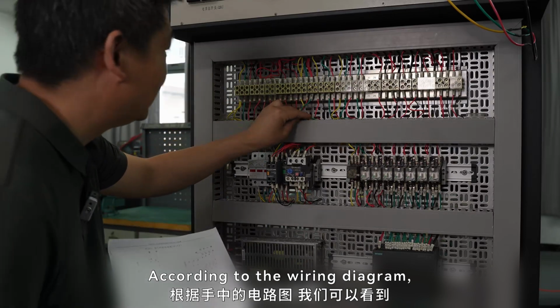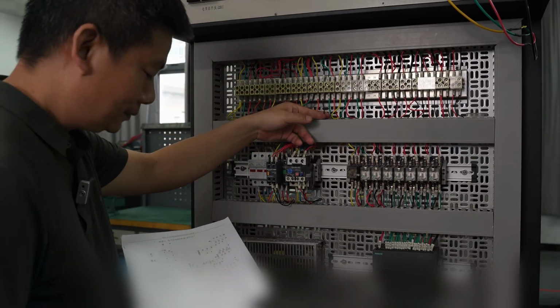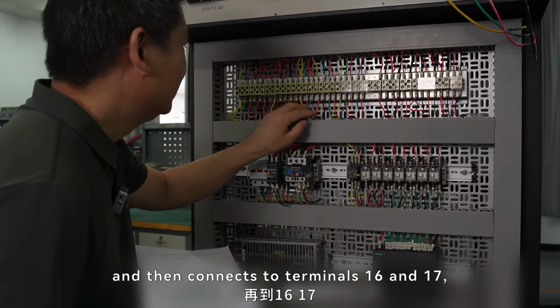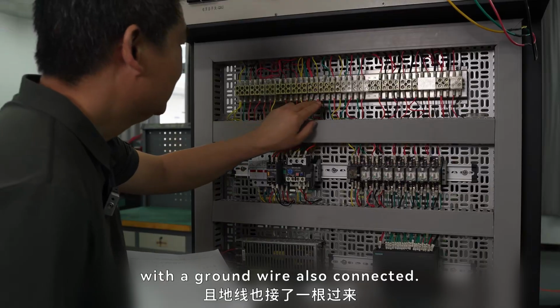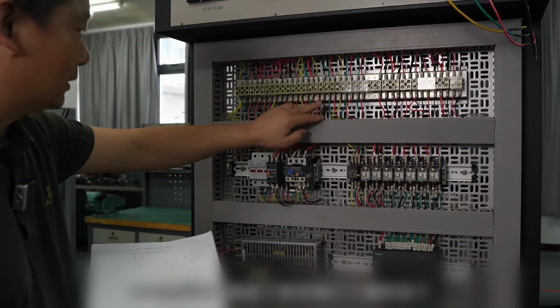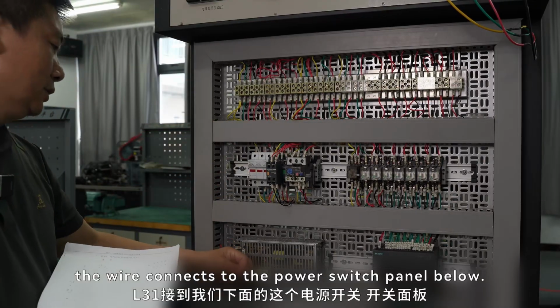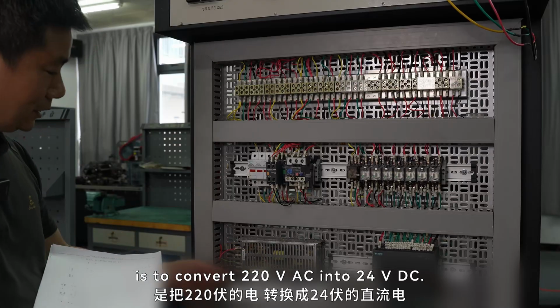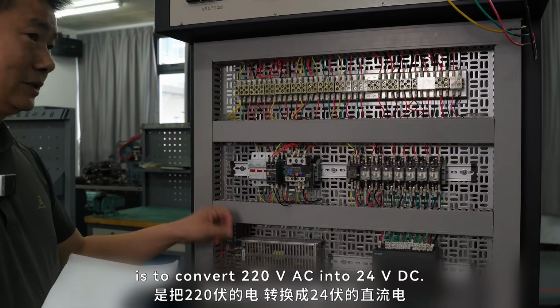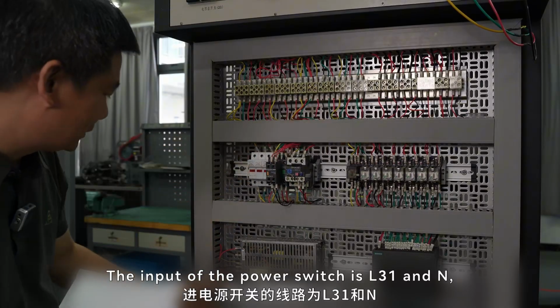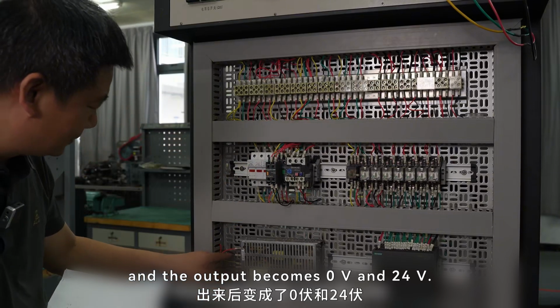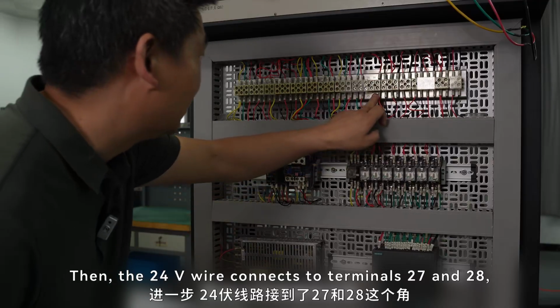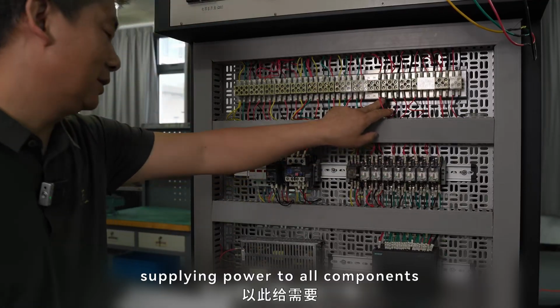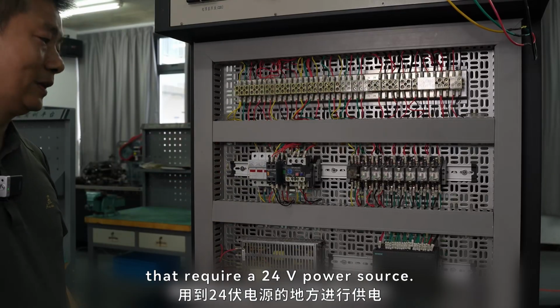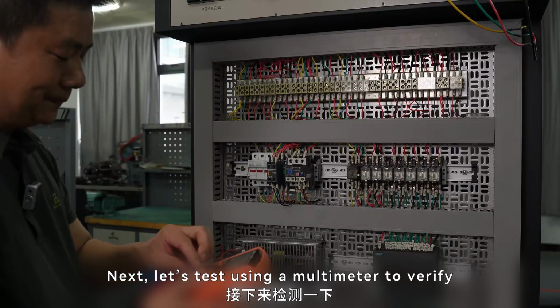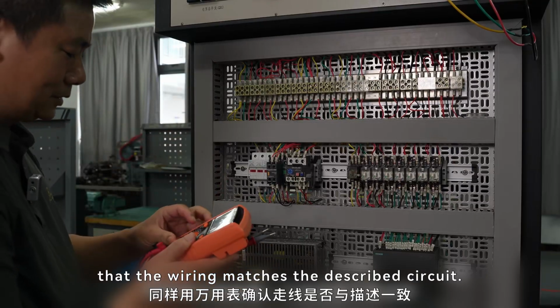According to the wiring diagram, a wire branches out from L31, goes through terminal 13, and then connects to terminals 16 and 17, with a ground wire also connected. From the junction at L31, the wire connects to the power switch panel below. The function of the power supply switch is to convert 220 volts AC into 24 volts DC. The input of the power switch is L31 and N, and the output becomes 0 volts and 24 volts. Then, the 24 volts wire connects to terminals 27 and 28, supplying power to all components that require a 24 volts power source. Next, let's test using a multimeter to verify that the wiring matches the described circuit.